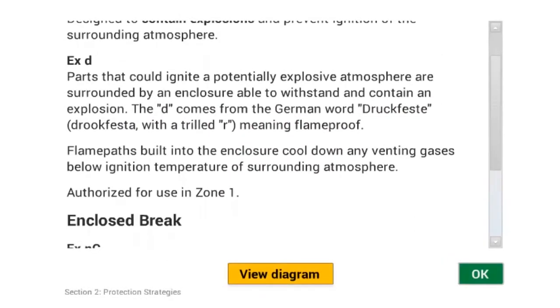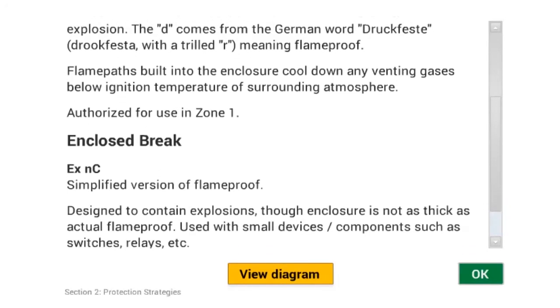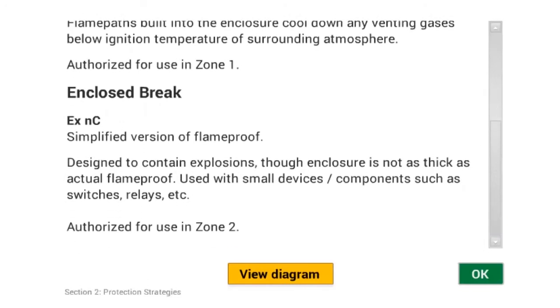The Enclosed Break Protection symbol is EXNC, with a lowercase n and a capital C. Please note that EXNC has multiple meanings. The important thing to remember is that this is a Zone 2 concept. Enclosed Break is the Zone 2 version of Flame Proof, but is limited to no more than 100 cubic centimeters of internal volume.